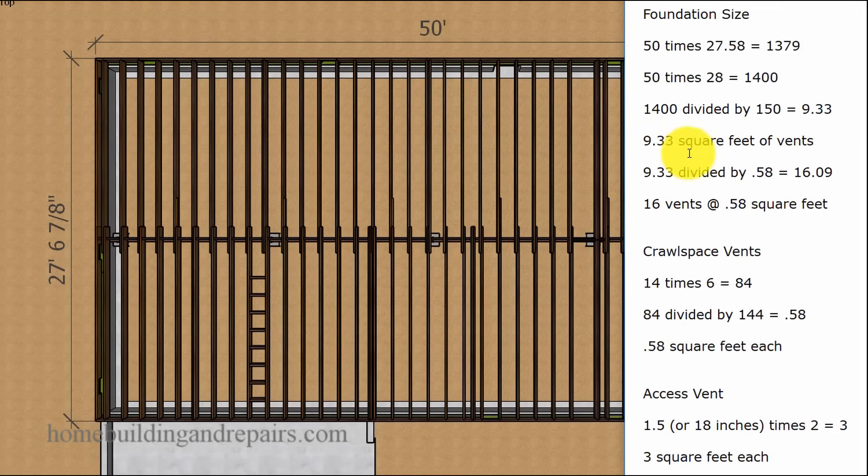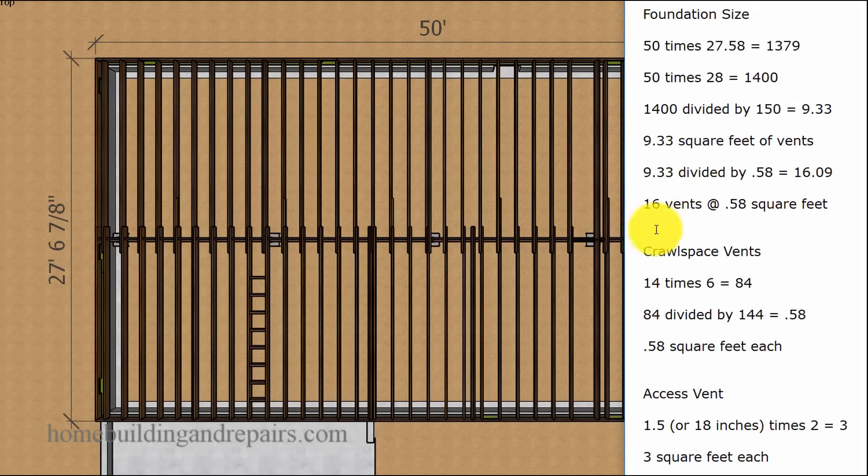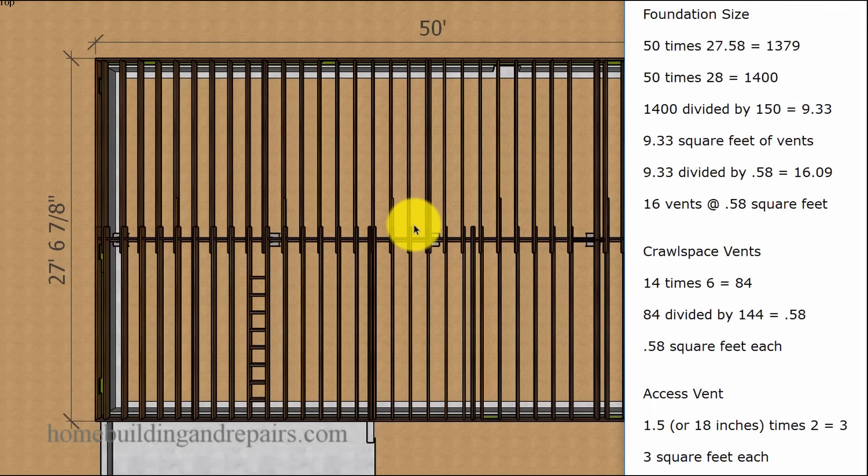That's the square footage of vent area we need. 9.33 divided by 0.58 gives us 16.09. That is how many vents we are going to need for this particular building foundation.